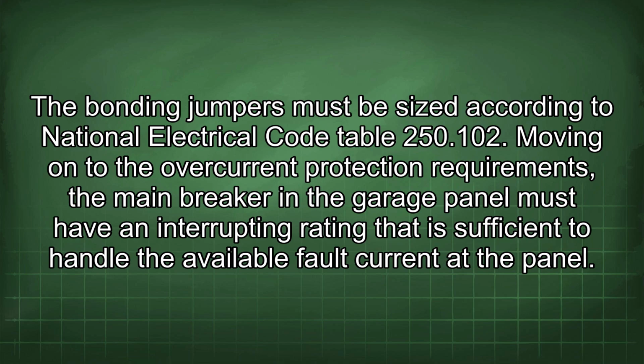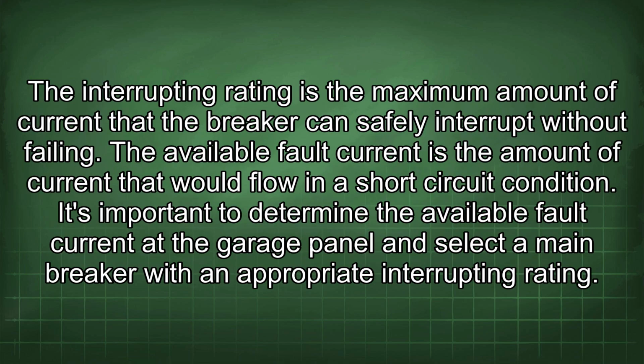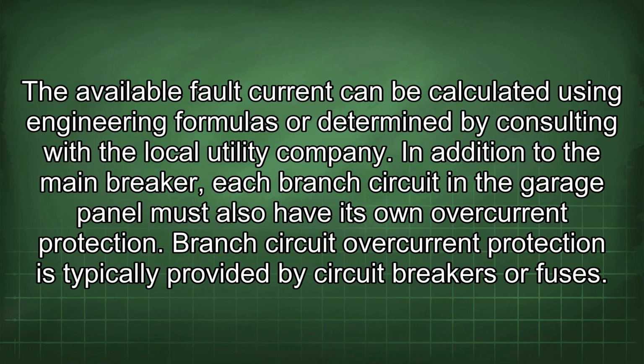that is sufficient to handle the available fault current at the panel. The interrupting rating is the maximum amount of current that the breaker can safely interrupt without failing. The available fault current is the amount of current that would flow in a short circuit condition. It's important to determine the available fault current at the garage panel and select a main breaker with an appropriate interrupting rating.